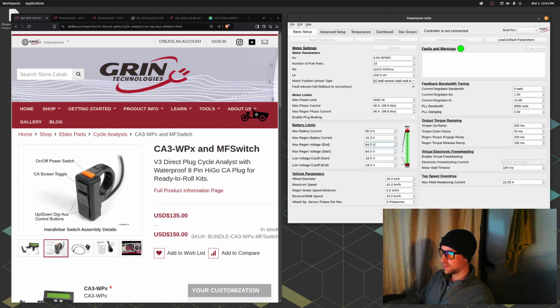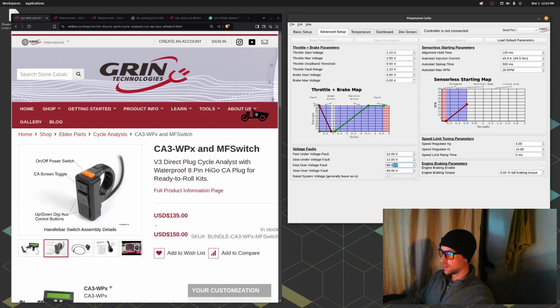Also under advanced setup, you want to make sure the fast over voltage fault and slow over voltage fault are set higher than your battery's full charge voltage.